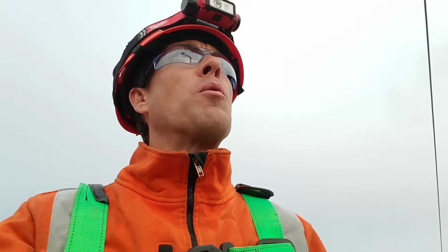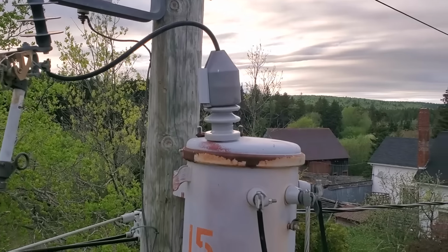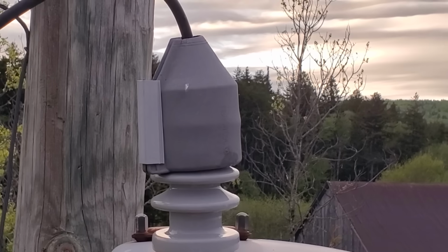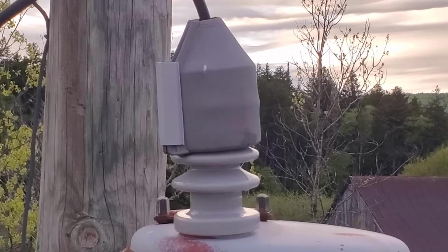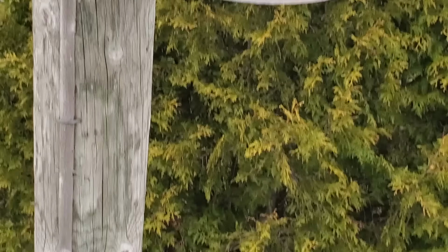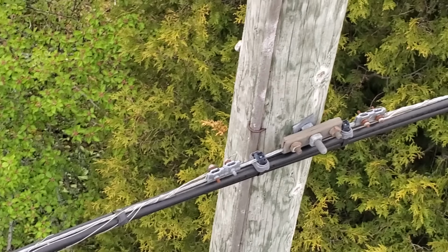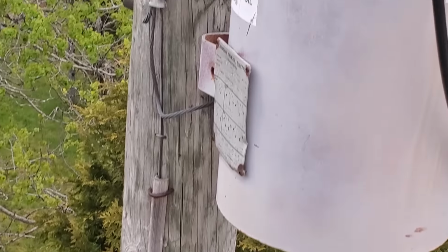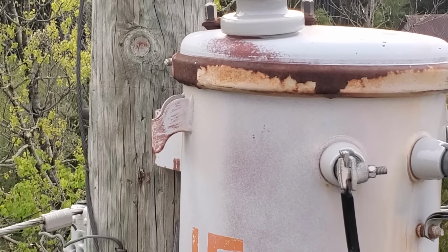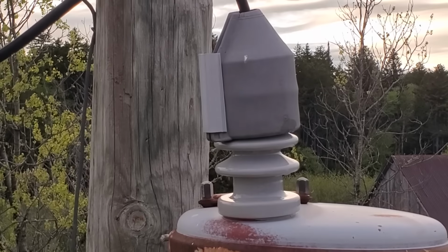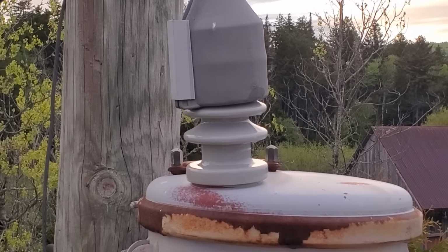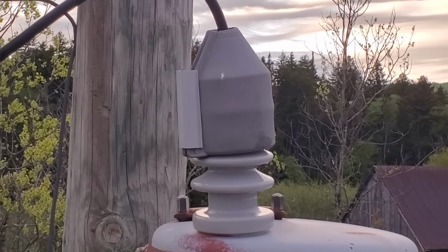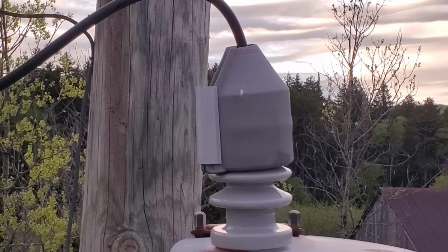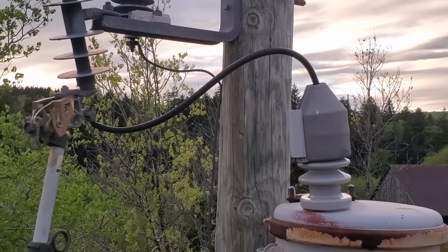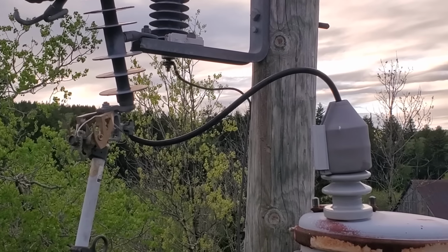Just a couple more things while we're waiting for Ryan to get all geared up. I'm going to mention on this transformer, see the primary bushing here has that gray cone over top, we call that a squirrel guard. Squirrels like to climb up the pole or use those telephone wires as kind of a highway system. They'll run up the pole, up onto the transformer, which is grounded through its case ground, up and over that bushing, and their back legs will be standing on the transformer lid while their top touches the 7200 volts on the bushing, and that'll cause the fuse to blow, and also that'll be the end of the squirrel.